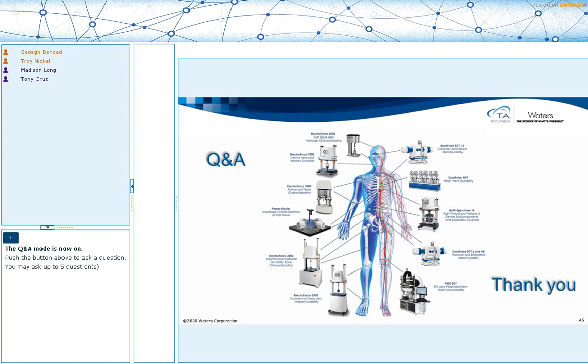So that's easy. You're always looking at your load, right? So if your sample is touching the upper surface of your material, you will sense the compressive load. So if you exert and maintain a negative load at all times, no matter what the sample height is, you have ensured that you are staying in contact with your sample.